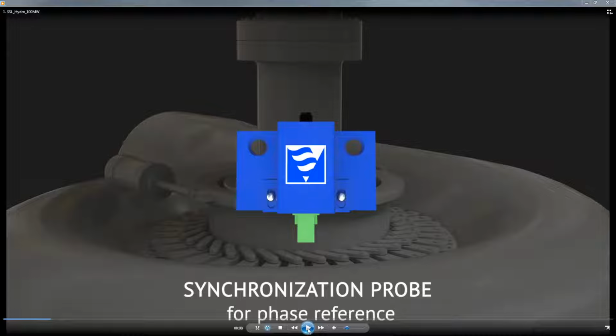For pump storage units, which rotate in both directions, you do need two to give you the proper position in both directions. That probe is usually, and this is strongly recommended, installed in the turbine pit. The reason for that is that if you need to make some adjustments, it's very easy to go there and make those adjustments without having to dewater the unit and have all the locks and the security process in play. So the best place to position that is in the turbine pit.